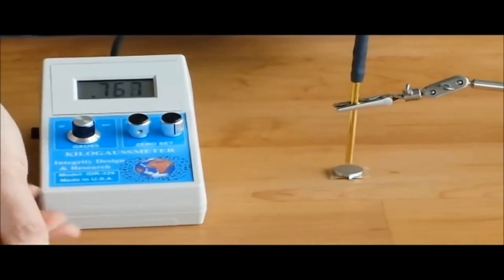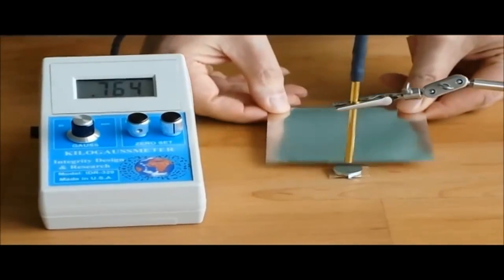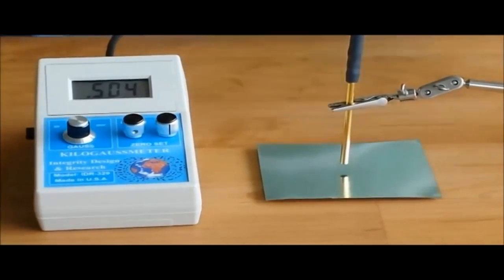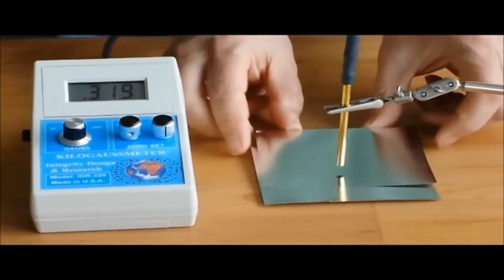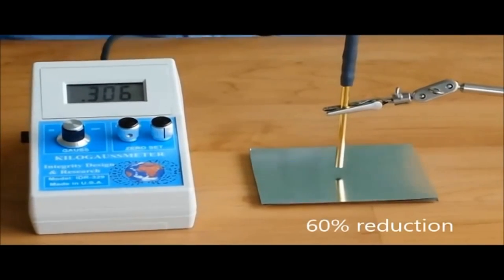Now, if instead I use a larger piece, same material, same thickness, just a larger format, one layer drops us to 504. With a second layer of magnet shield, it drops us to 306.